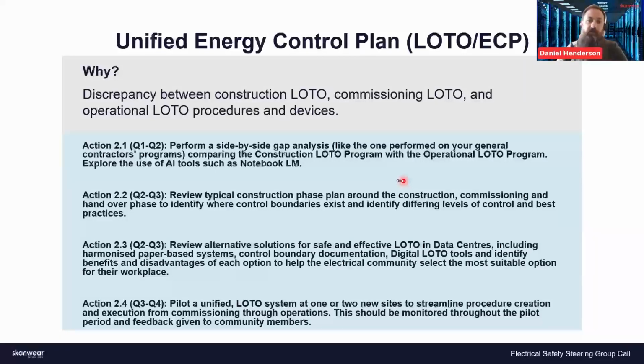But yeah, so for your point there, typically you'd expect if it's in construction that they would have done a level of Arc Flash survey. It might not be finalized - you'd expect it to be finalized on completion, when they know the final cable length, so you'll know your set impedances, and the relay types might have changed over time from the original design to installation. So you will know at that point, you should know everything. So it's ensuring that comes over in the handover process.